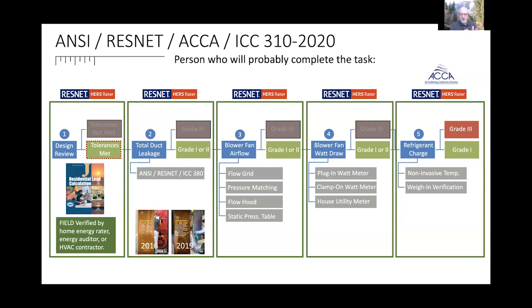These are supposed to go in order: 1, 2, 3, 4, 5 - do this, confirm that, you pass, move to the next one. But sometimes 5 is done before 2. The system gets installed and charged, ready to go, probably providing dehumidification or cooling during install, hopefully with registers covered. Then you go back and do 2, 3, 4, and return to 5 to confirm the weigh-in. So if you were on top of your game, you had your contractor do a great job weighing it in from the start.